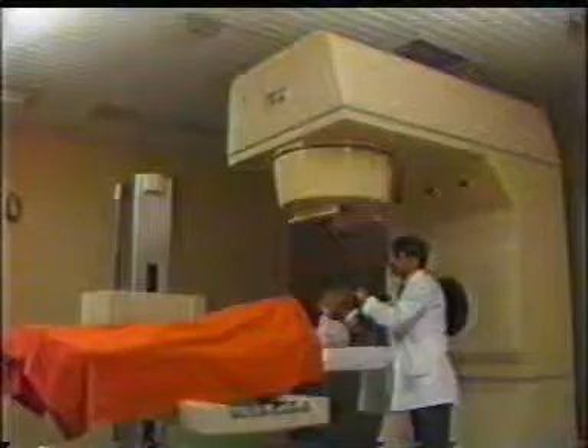The other definitive advantages are: linear accelerator saves the skin and subcutaneous tissues more efficiently. Because with 4 MV linear accelerator, the maximum buildup is 10 to 13.5 millimeter below the skin, as compared to 5 millimeter in case of cobalt-60. There are three distinct advantages in this: in delivering dose in face and neck areas, for treating of larger fields as in Hodgkin disease, and for delivering booster doses.